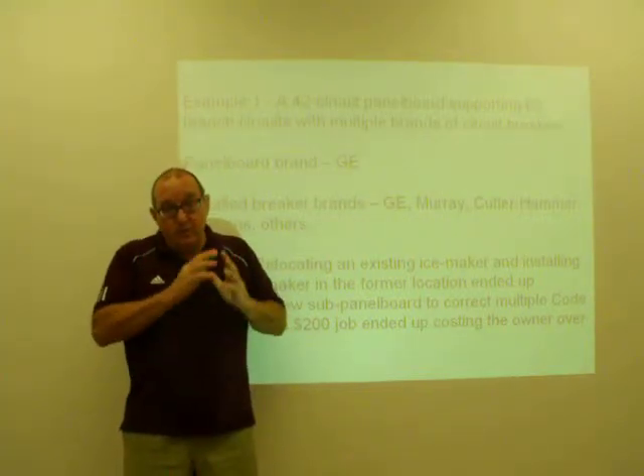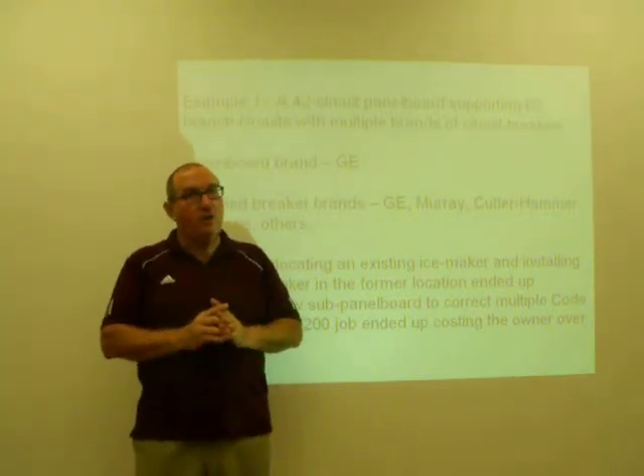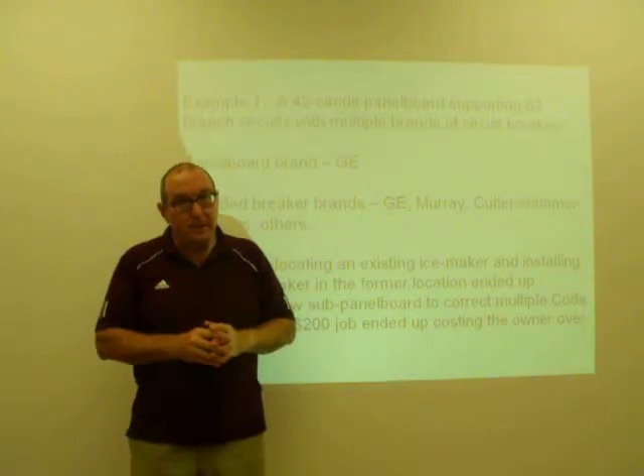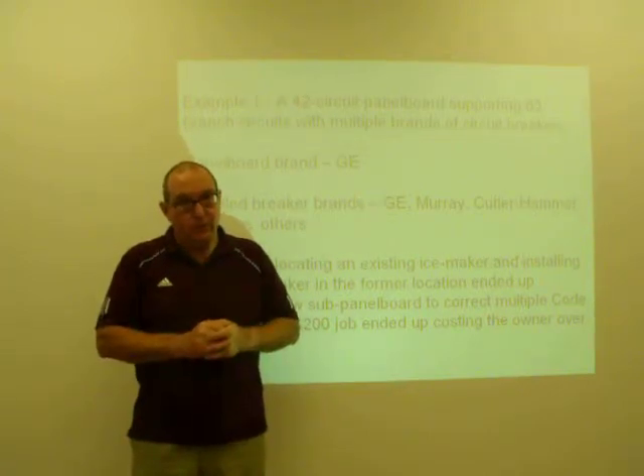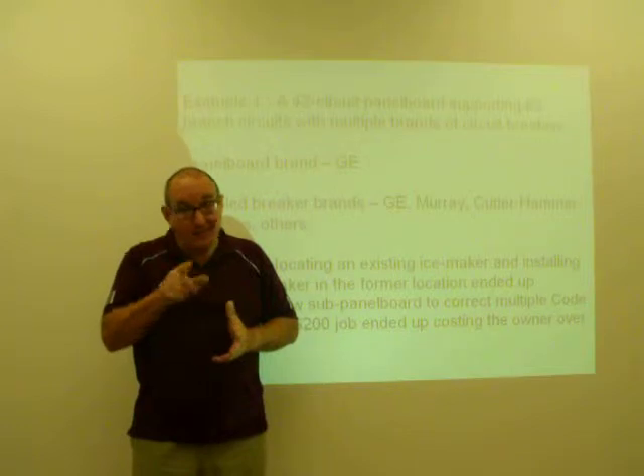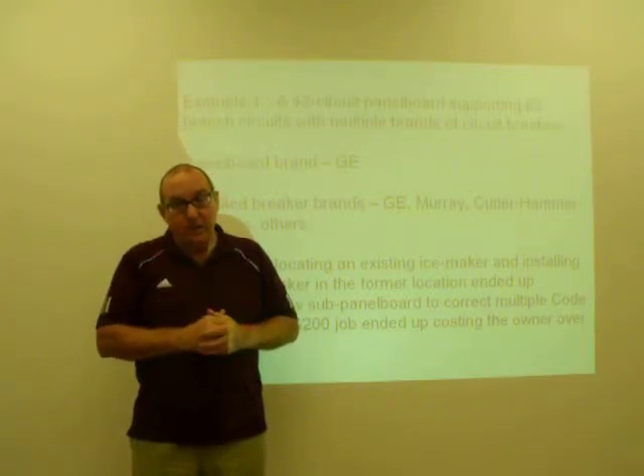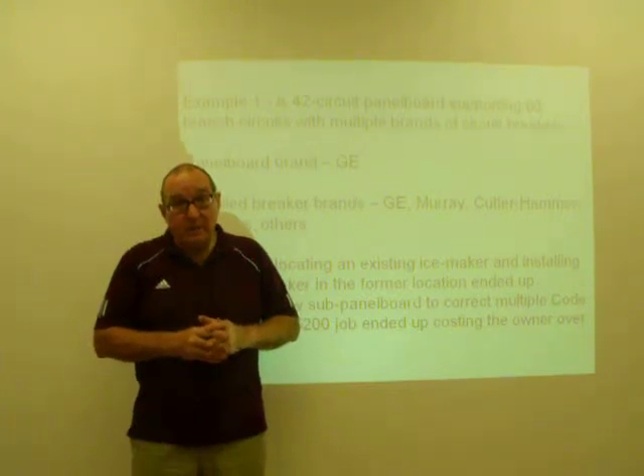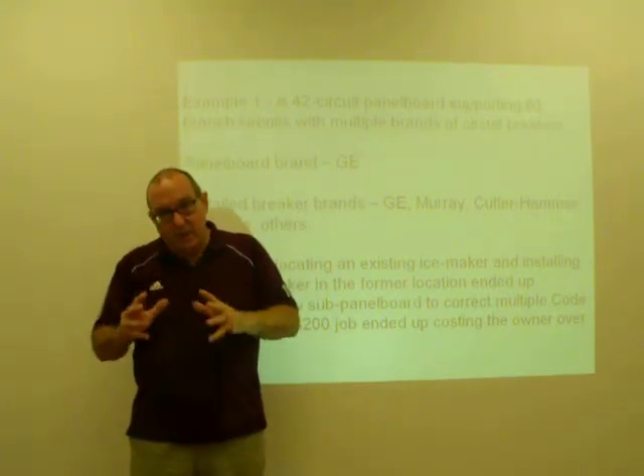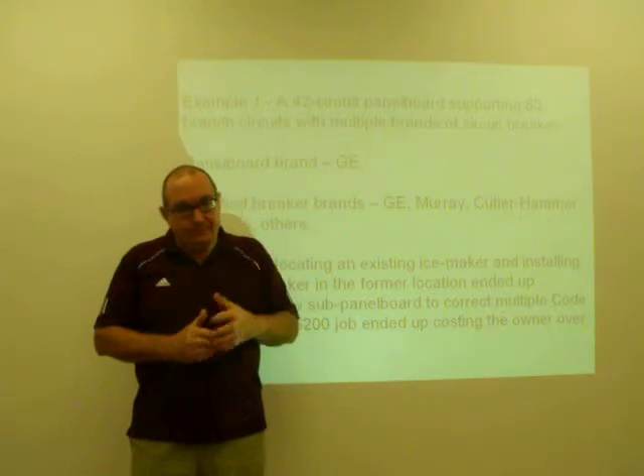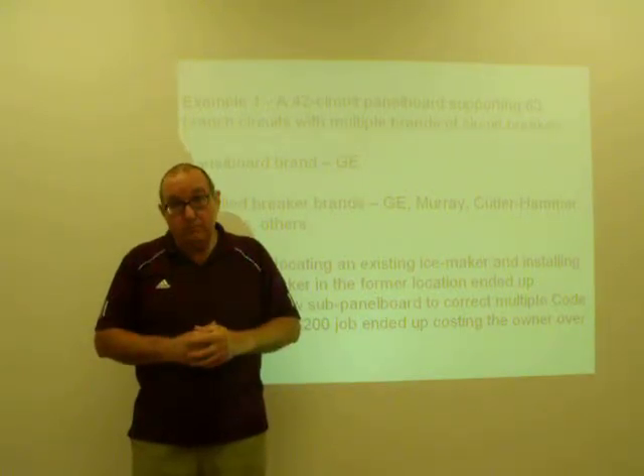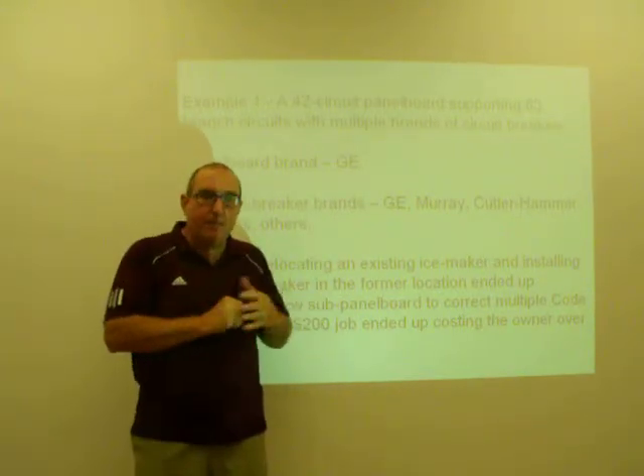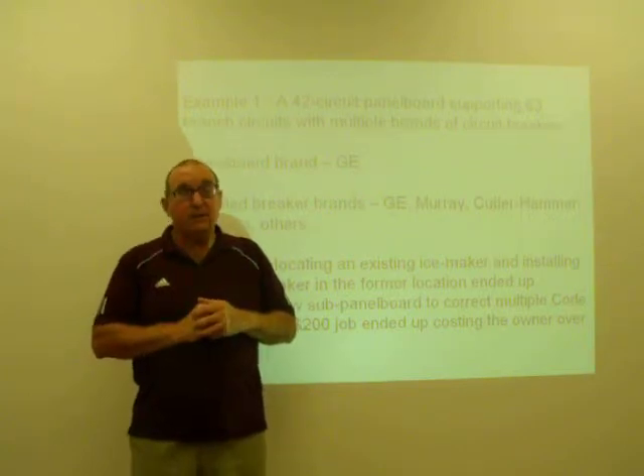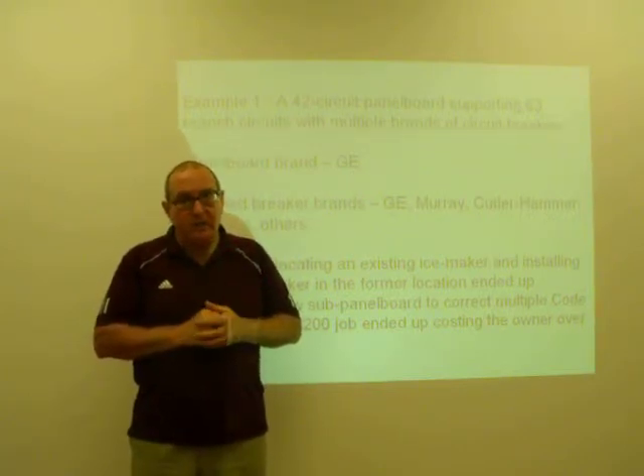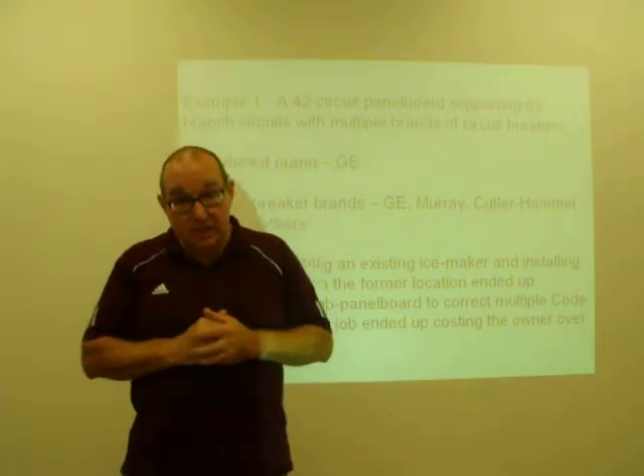The challenge I ran into was that when I got to that panel board, I found all these code violations. I told the owner, I cannot do what you want me to do unless I fix all these other violations. So a job that maybe should have been a few $100s ended up requiring that I install a sub-panel and $5,000 worth of work. So that mistake made by a previous electrical contractor, and I'm using that term loosely, cost this owner a considerable amount of money.